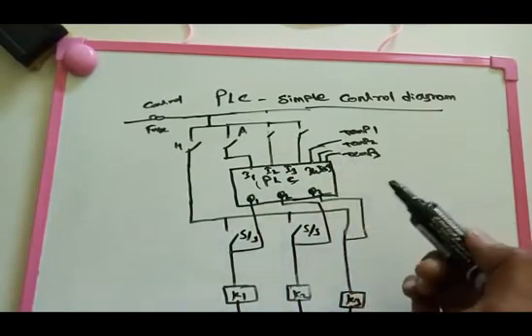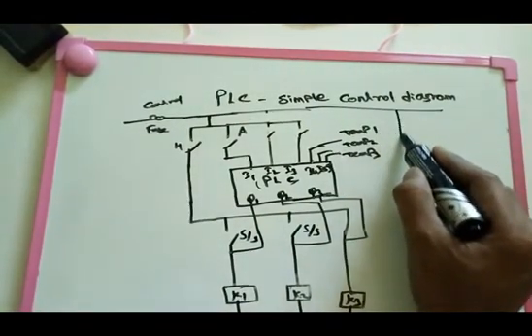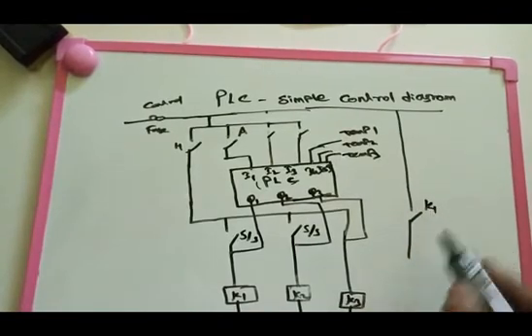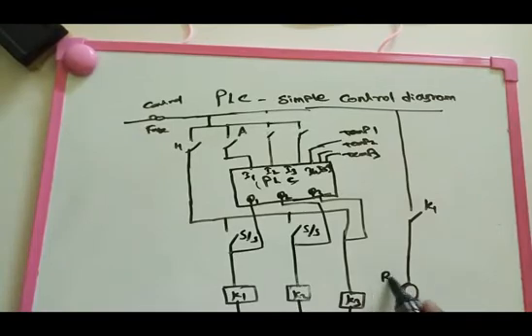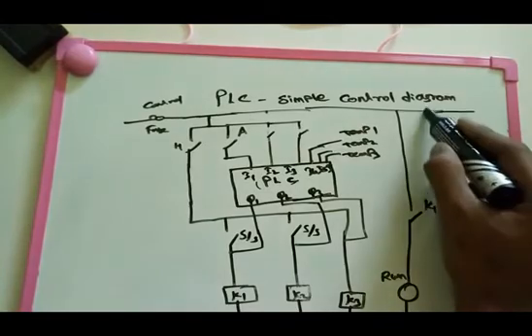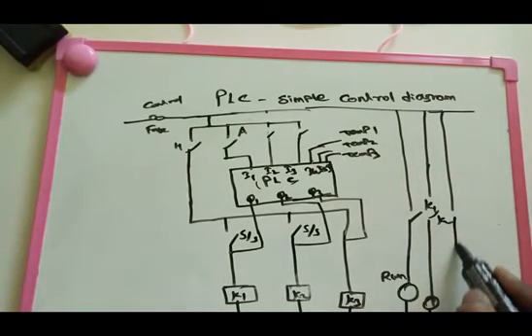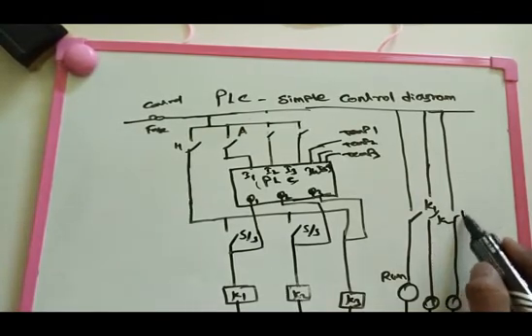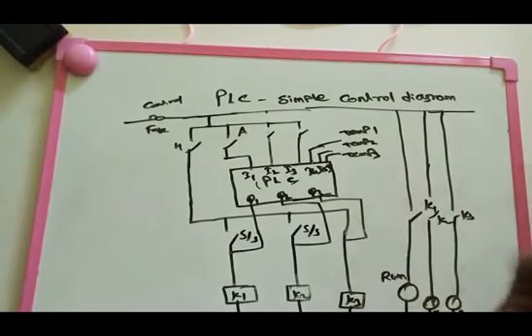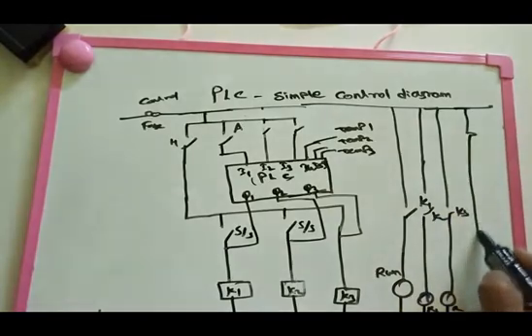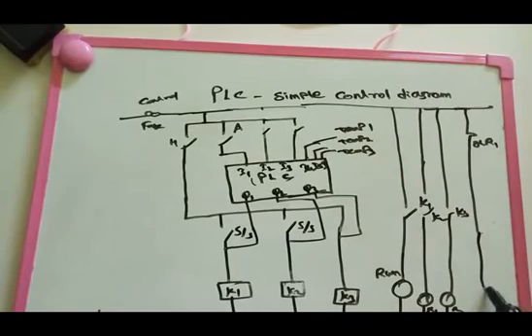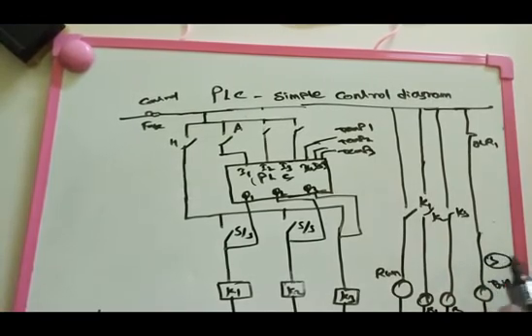After that, we indicate which AC is running. For K1, we make a CNO contact to switch on a run indication lamp. Similarly we make K2 and K3 indication lamps for AC2 and AC3. After that we need trip signals — we use OLR1 to make a trip lamp. Like that we make three trips for all three ACs. This is the complete diagram of simple PLC control. Thank you for watching.